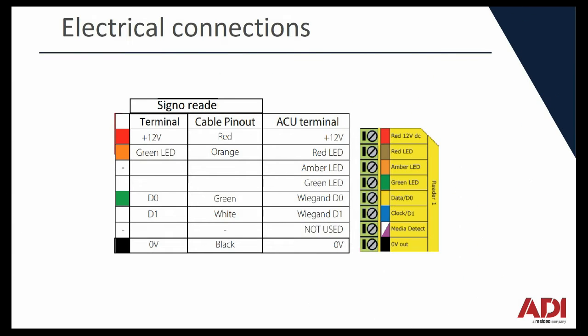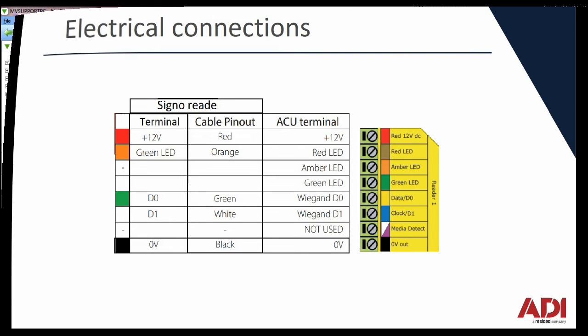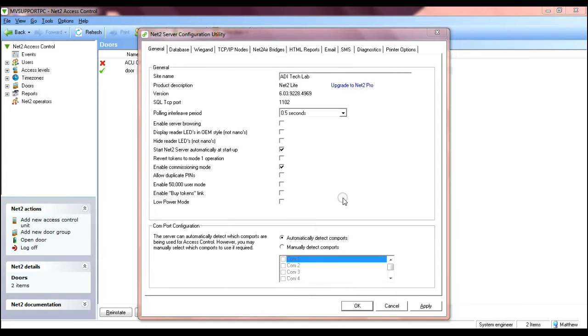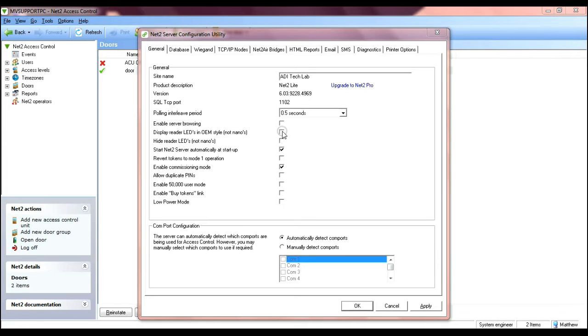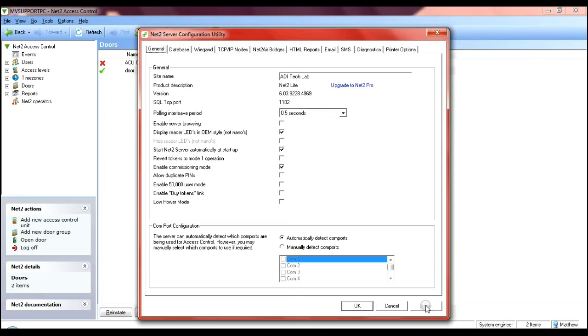Then we can move on to the Net2 device and do some configuration here. What we're going to do is have a quick look at the wiring, how it's set up. You can see there the simple connections. Launch the Net2 server configuration utility and all we have to do here is change the LED behavior and we're just going to change it to LED to OEM style. Once you've done that, click apply and that changes the way the LED operates. Instead of the pulsing flash which you normally have with Net2, it'll be a constant light to show access granted.